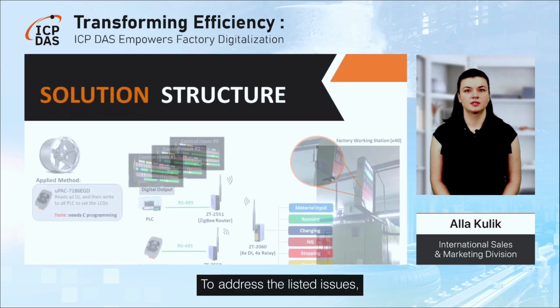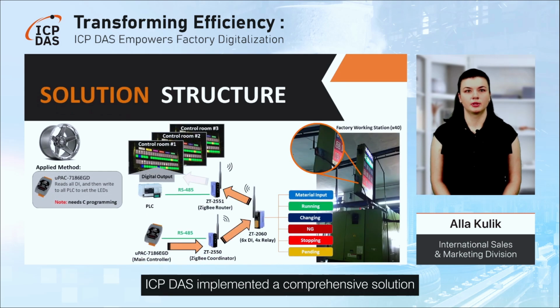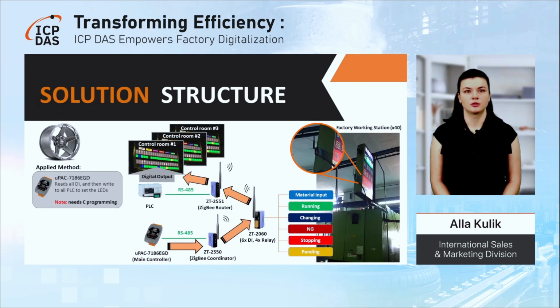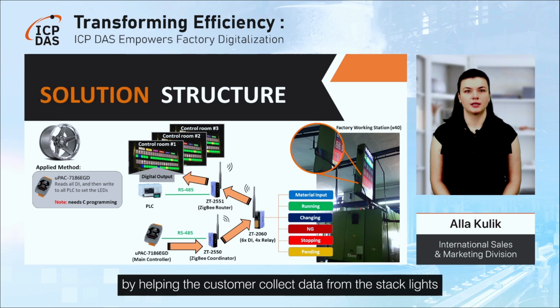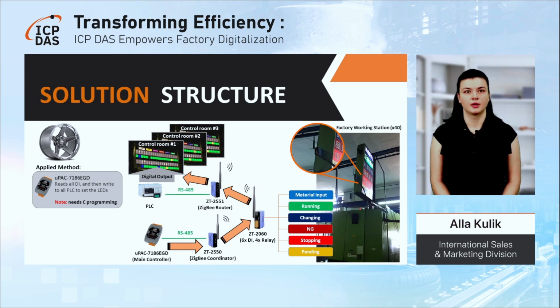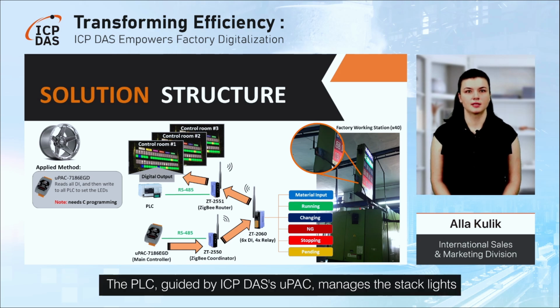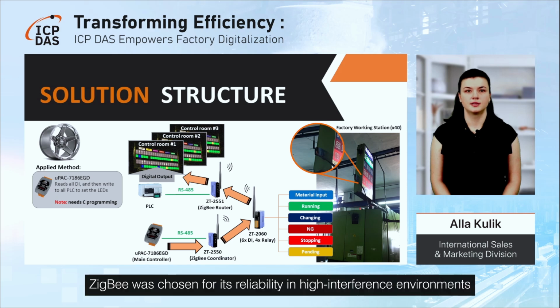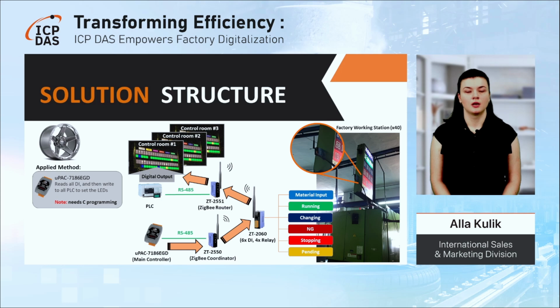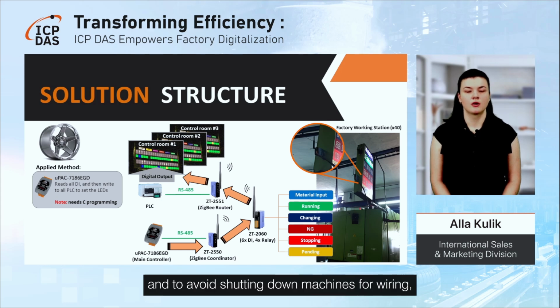To address these issues, ICP DAS implemented a comprehensive solution by helping the customer collect data from stack lights and transmit this data wirelessly via ZigBee modules to the PLC. The PLC, guided by ICP DAS's uPAC, manages stack lights to clearly display each machine's status to management staff. ZigBee was chosen for its reliability in high-interference environments and to avoid shutting down machines for wiring, thus reducing operational disruptions.